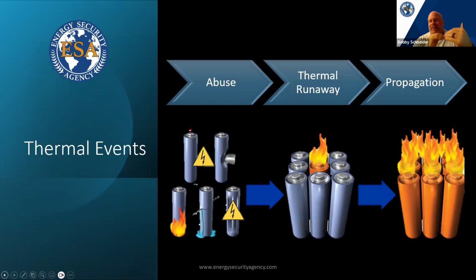Electrical abuse is where the battery pack or cell gets the wrong amperage or voltage, either input or output, than it's rated for. So if you have an onboard charger or a management system—whether it's an e-bike, a vehicle, or a large system—if something happens with the system that oversees what comes in and goes out, and it allows overcharging or the wrong voltage or amperage to be exposed to that battery pack or cells, that can generate heat. That heat causes the organic solvent to heat up, off-gas, build pressure, and degrade the separator. Then again we go from that domino effect to a thermal event, thermal runaway, and propagation.